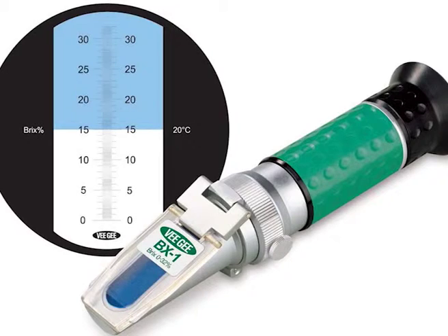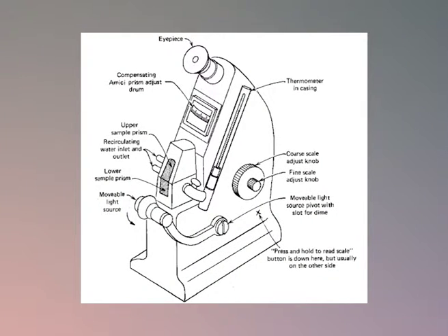Then you have the refractometer. It is a laboratory or field device for the measurement of refractive index using the very famous Snell's law. The main type of refractometer is the Abbe refractometer. The only thing is that the methods involving an Abbe refractometer require pieces large enough to polish. It has built-in thermometers and requires circulating water to cool the instrument and fluid temperature. Dispersion can also be measured by an Abbe refractometer.